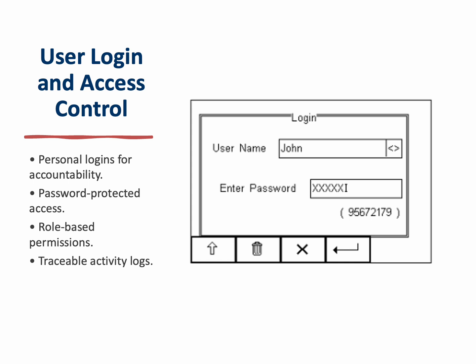Access control on the Rigel 288 Plus ensures that every test can be traced back to the operator who performed it. Each engineer can have a personal login, maintaining accountability within the maintenance team. Passwords protect sensitive configurations from unauthorized changes. In larger institutions, administrators can assign role-based permissions, allowing some users to perform tests but restricting access to calibration or system settings. Activity logs are stored with each session, creating a digital paper trail for quality assurance and audits. This feature is subtle but critical. It transforms the Rigel 288 Plus from a simple tester into a controlled instrument within a compliant biomedical system.